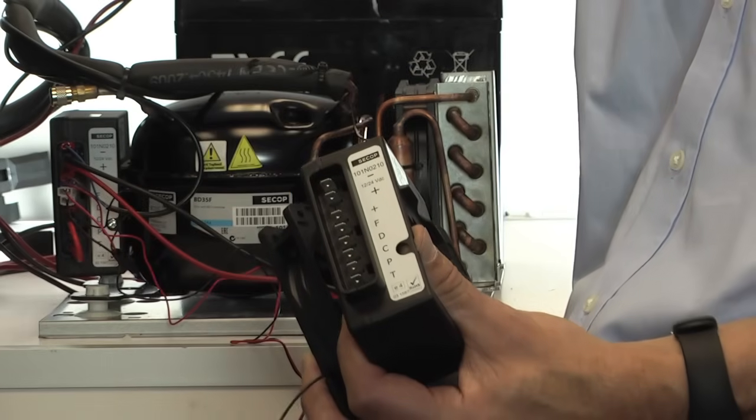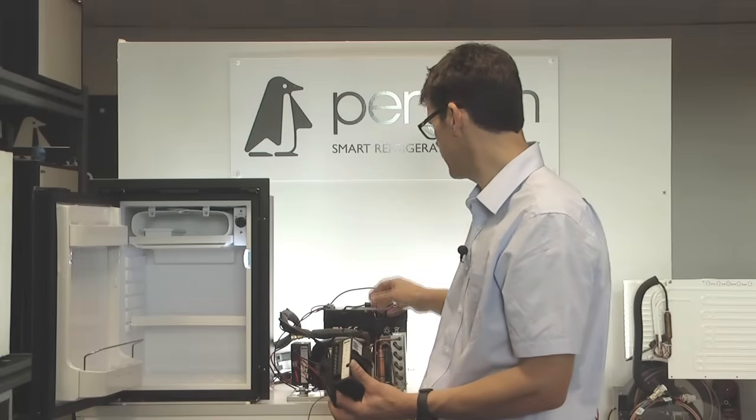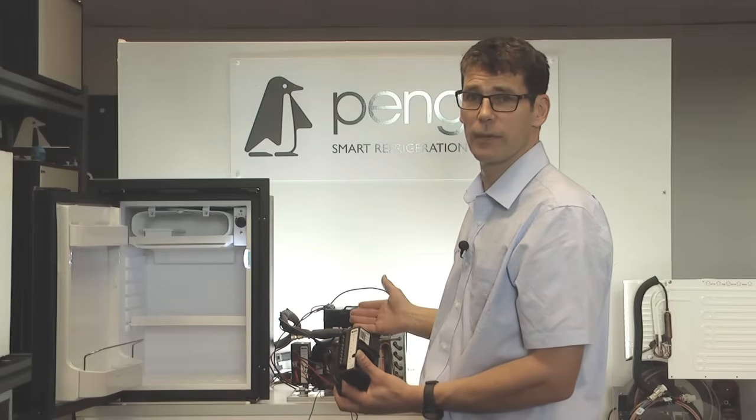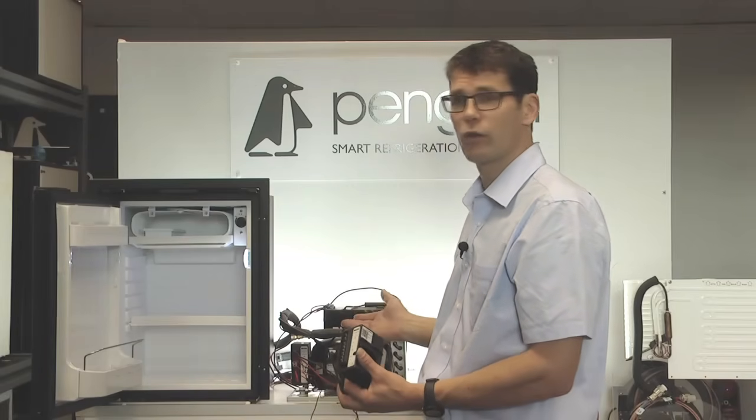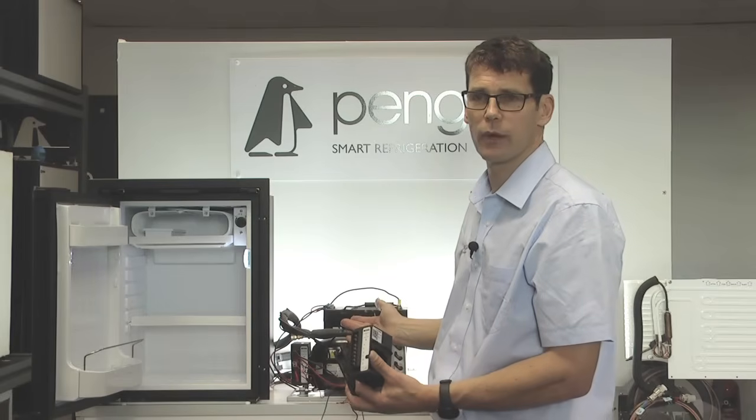If we disconnect one or both of those, the compressor starts, we know that the problem is the fan. It's then a question of removing the fan, confirming the size, and then you can order a replacement online at our website, www.penguinfrigo.co.uk.